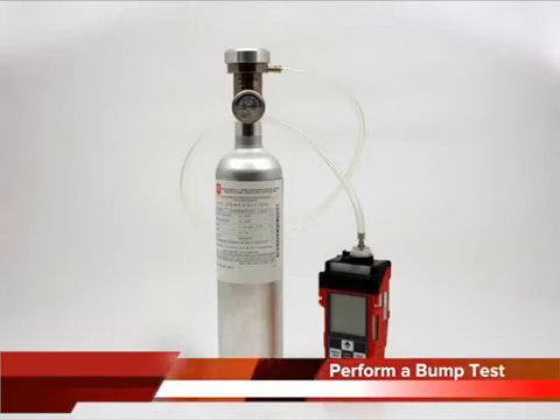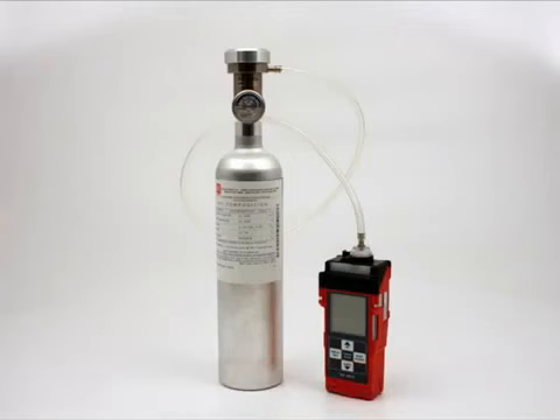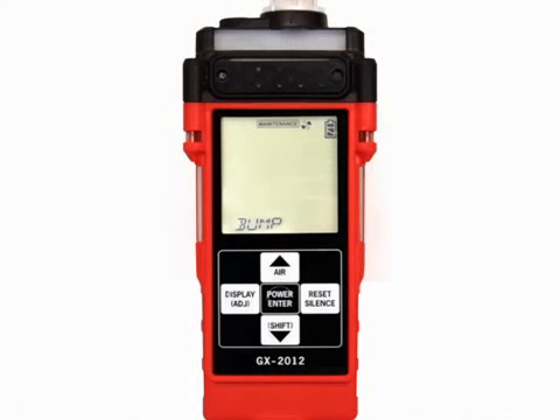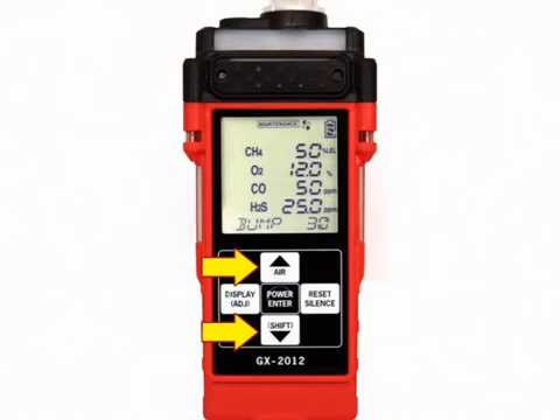Install the demand flow regulator onto the calibration cylinder. Connect the sample tubing to the demand flow regulator. Use the air or shift buttons to display the bump menu item. Press and release the power enter button to display the bump test gas values. Use the air or shift buttons to see the percent volume combustible gas bump test value.